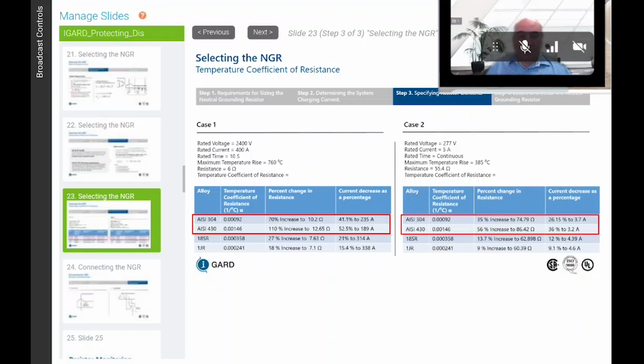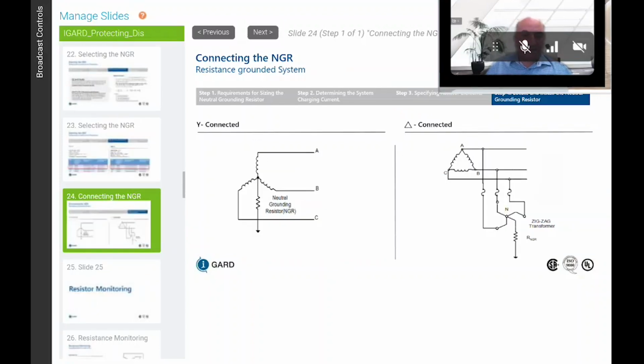So these two elements violate the rules in C57.32 and C295 CSA. So if you have a resistance grounded system and you have a Y-connected source, the easiest thing to do is just put a resistor between the neutral point and ground, and you want to limit the fault current. Remember, all fault currents have to return back to the neutral.